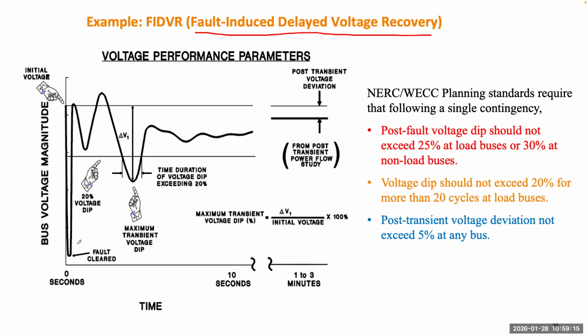So you can see there's a plot. This curve just indicates a typical curve after any single contingency. The Y axis is the voltage magnitude, the X axis is time. After the fault is clear, this is the lowest voltage magnitude. The standard says the post-fault voltage dip, which is the lowest voltage after the fault is cleared, should not exceed 25%, which means this voltage should be 0.75 per unit based on the base value. So if this substation is 230 kV, the lowest voltage will be 75% of 230 kV. It cannot be lower than that.